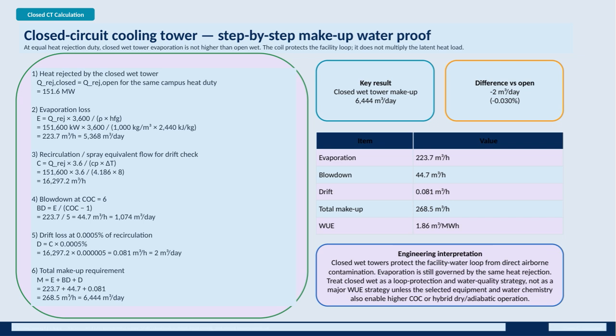Next, considering recirculation or spray equivalent flow for drift, we get a value of around 16,297 cubic meters per hour. The blowdown rate at a cycles of concentration of 6 is 44.7 cubic meters per hour, ensuring that water quality is maintained. Drift loss is minimal, just 0.081 cubic meters per hour, or around 2 cubic meters a day, which is only 0.0005% of the recirculation flow.